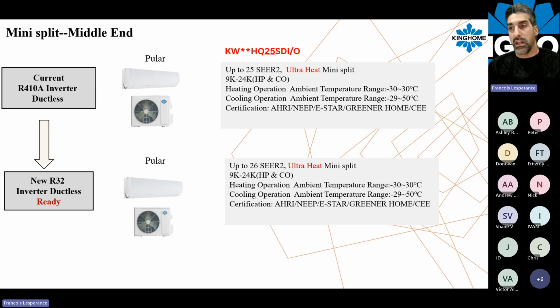So that's the kind of unit that you want to use if you have to do, like, a server room, low ambient cooling operation. It doesn't have to have optional kits. It's already good to go at minus 29 in cooling mode. Moving forward with the R32 series, this unit will be up to 26 SEER2, same capacity, same operation range.